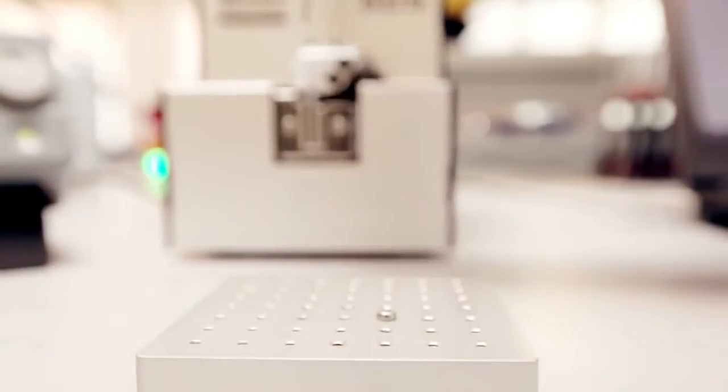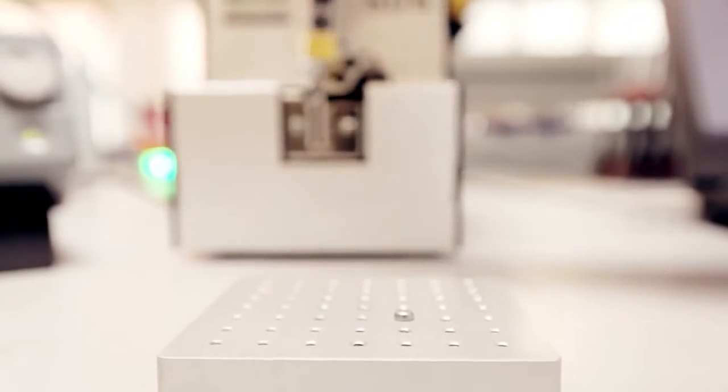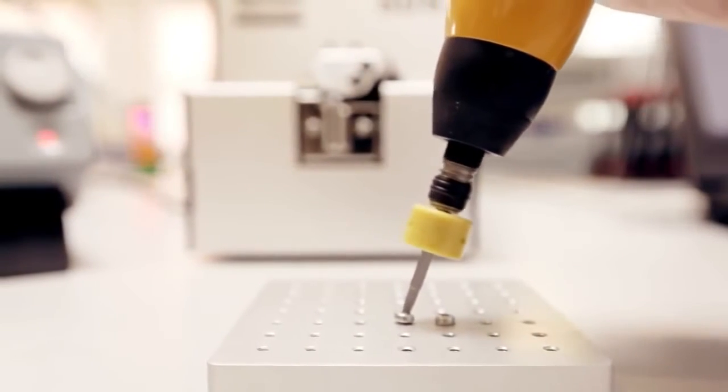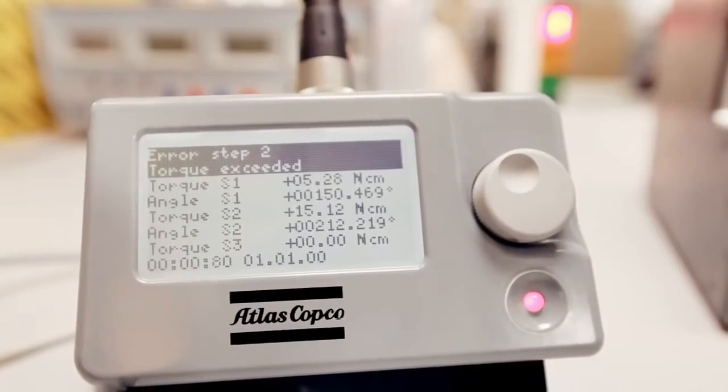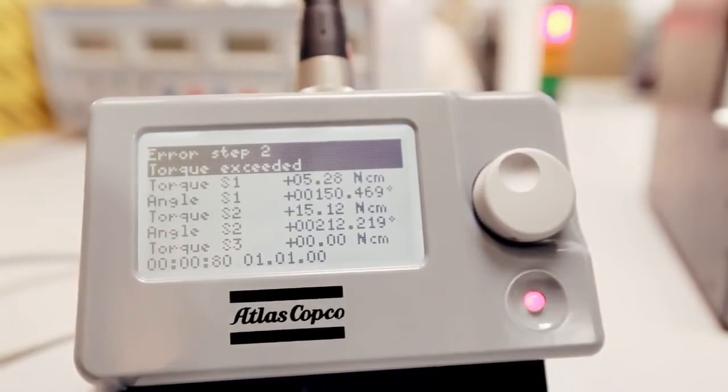A misaligned screw, a so-called cross thread, is detected by the fact that the tightening will reach final torque before the joint is tightened correctly. Torque is exceeded and the angle is too low.